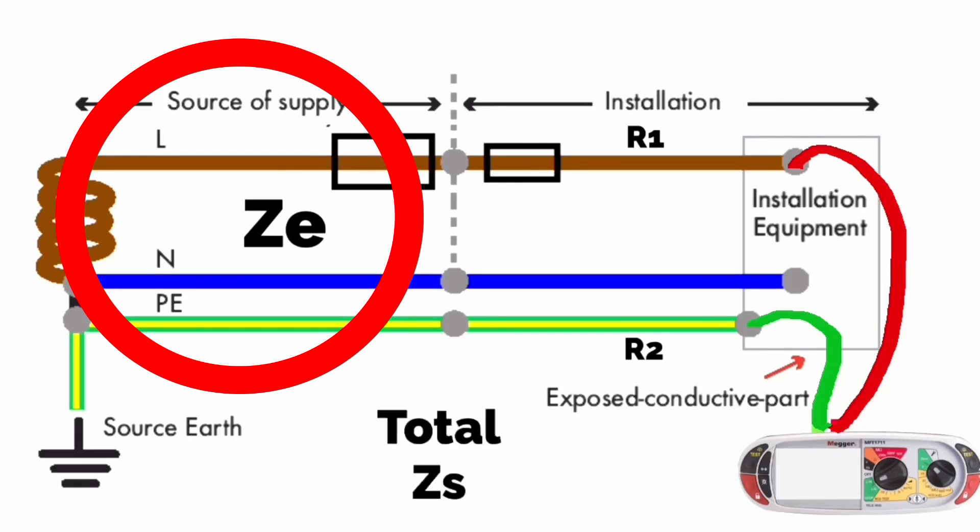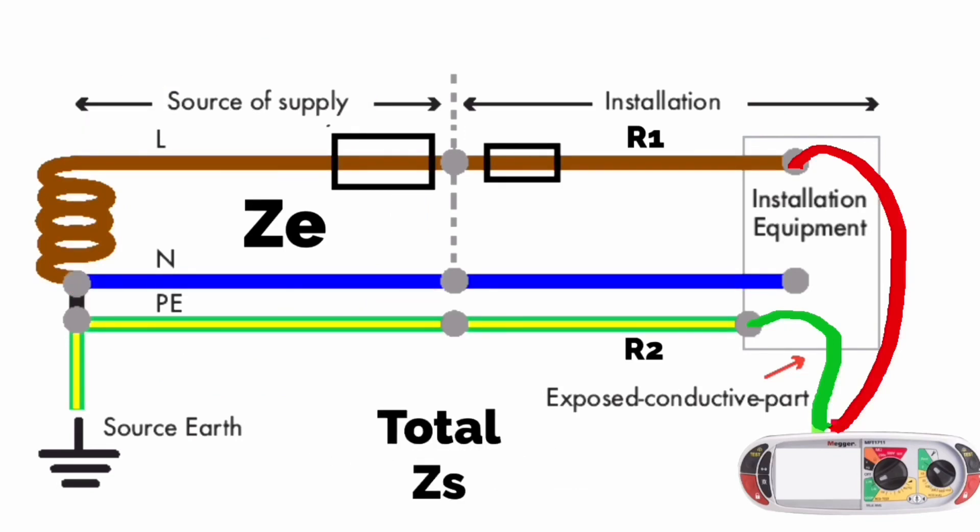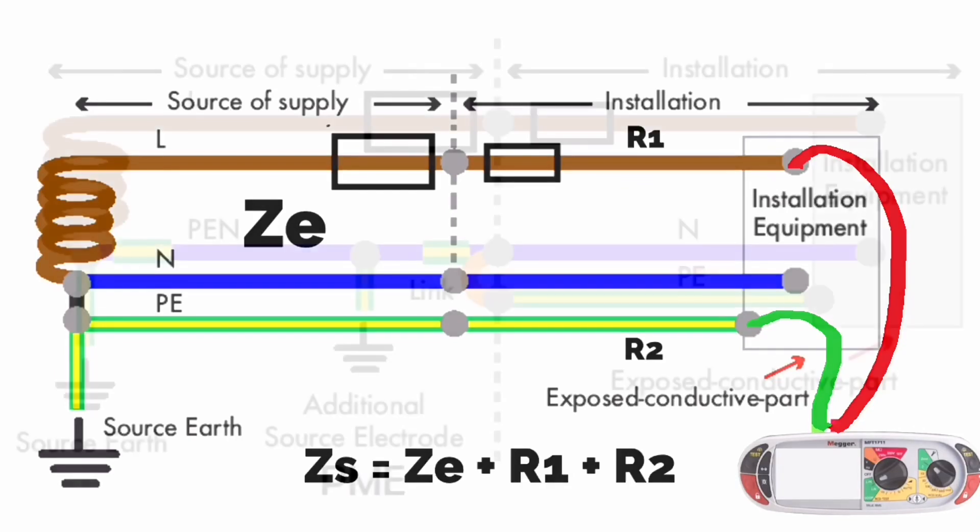The total earth fault loop impedance of a circuit measured in ohms is found by ZS, the total earth fault loop impedance, equals ZE, the supply authority's cable's impedance, added to R1, the line conductor's impedance, added to R2, the circuit protective conductor's impedance. The formula is ZS equals ZE plus R1 plus R2.